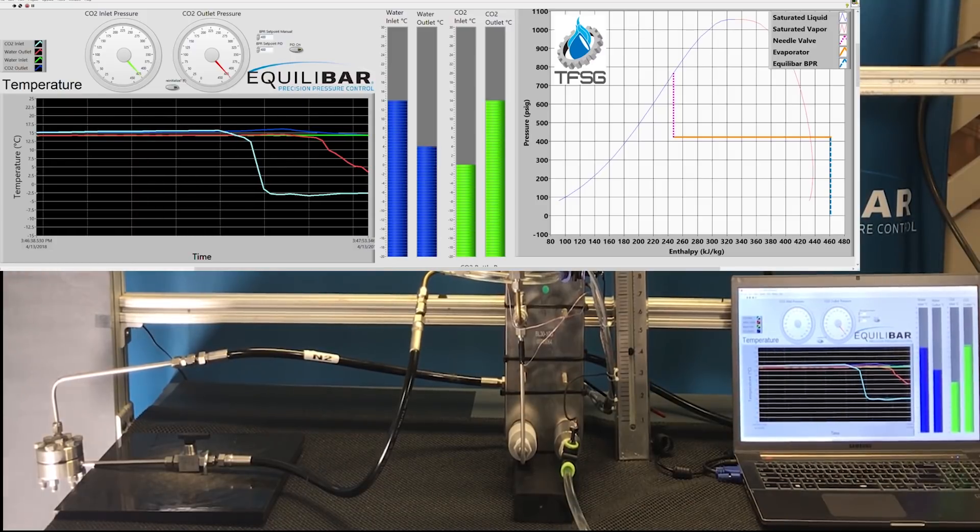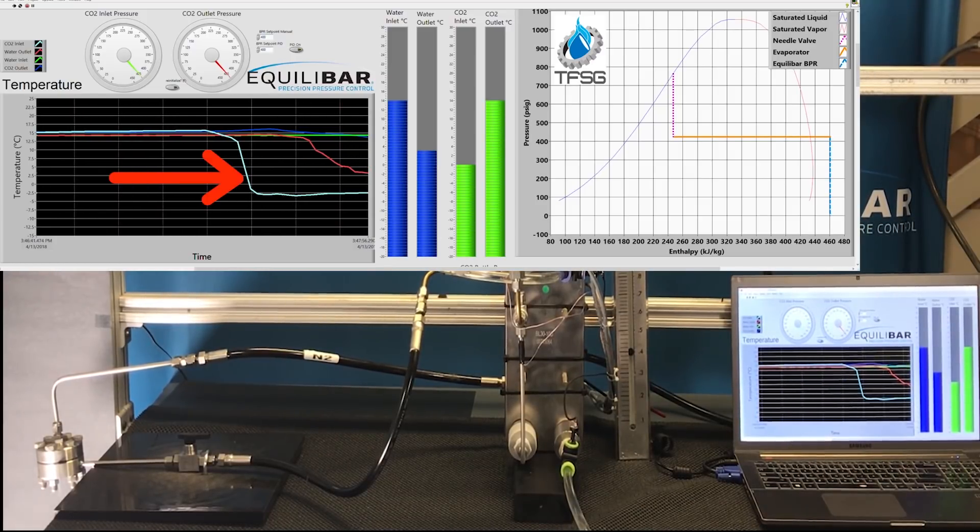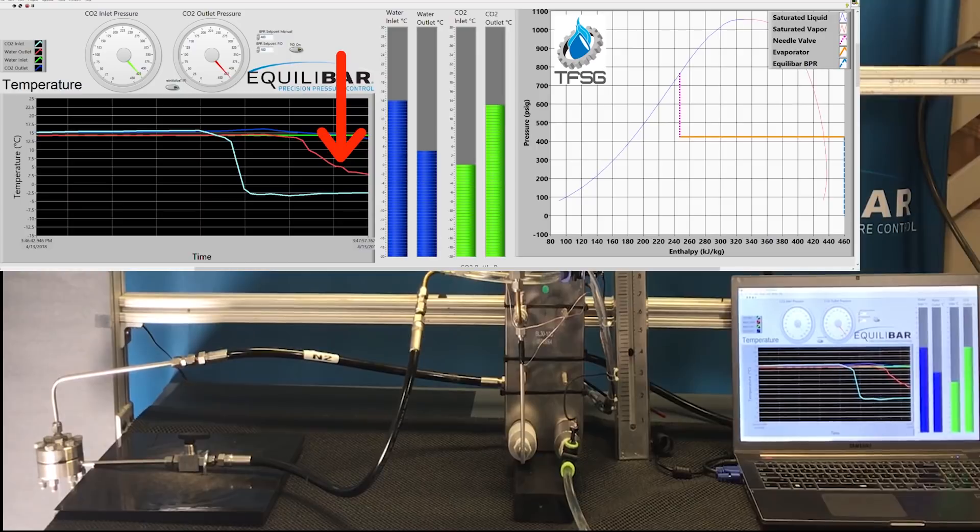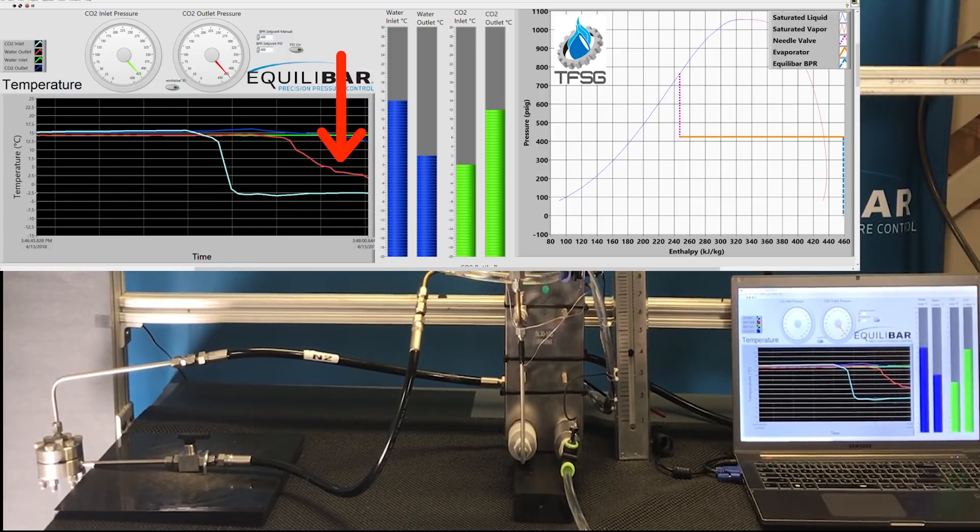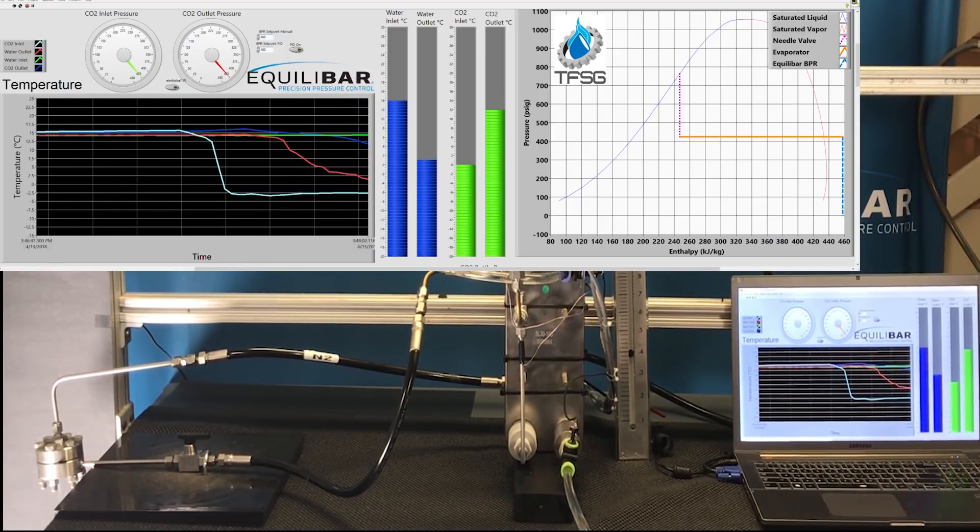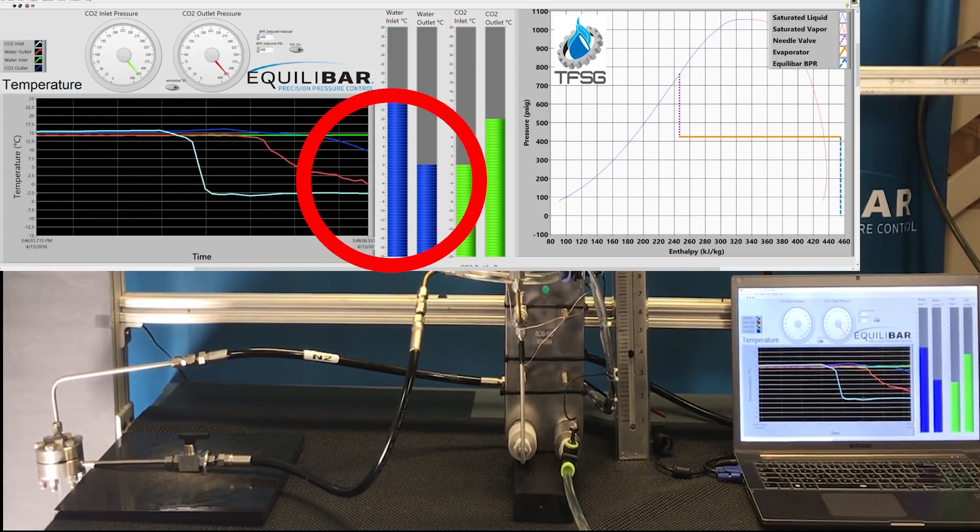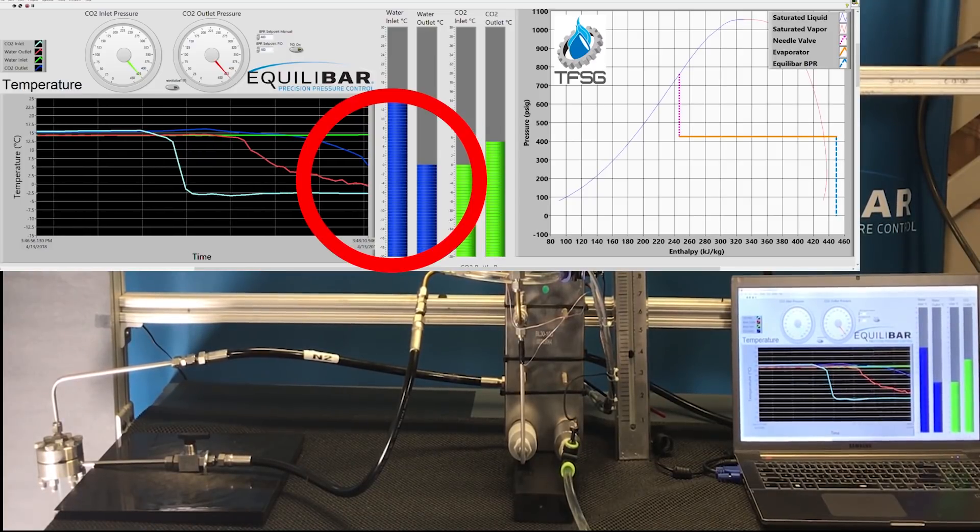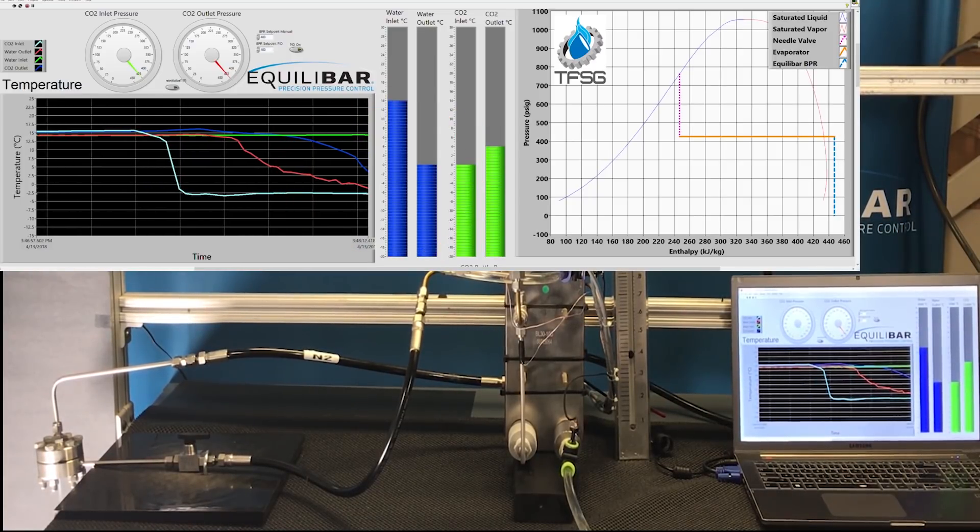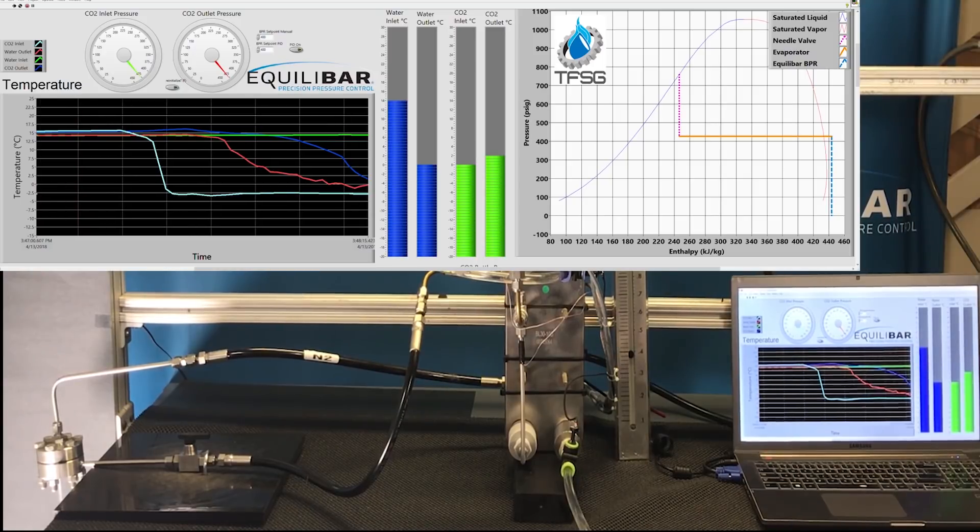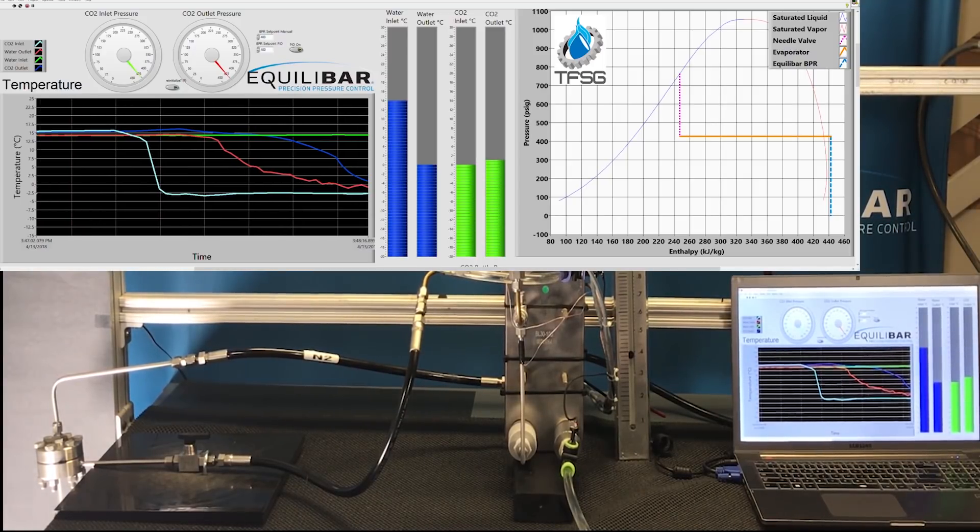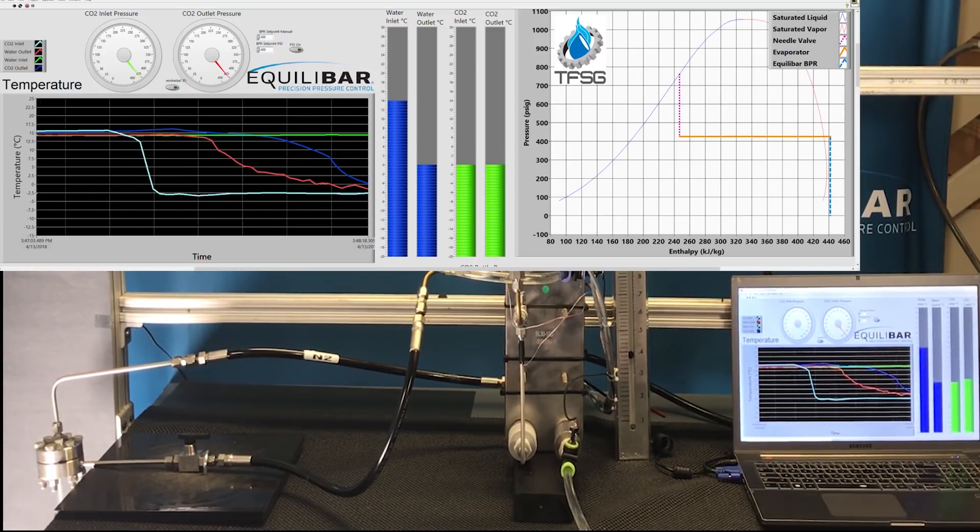To reiterate, the light blue line is the CO2 inlet temperature and the red line is the heat load outlet temperature. As the heat transfer process reduces heat load outlet temperature, convergence of these two lines will conclude isothermality. Equilibar's blockage resistant regulator design prevents the solid particles from plugging and allows them to exit without disturbing the pressure control. We can see this on the left side of the screen.